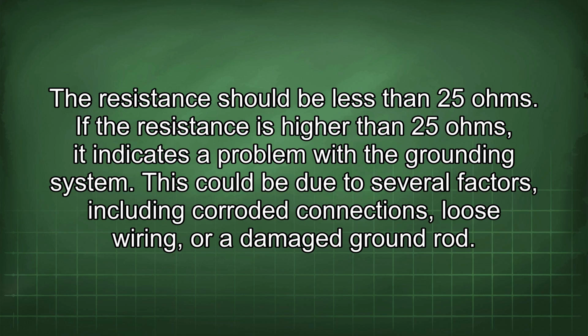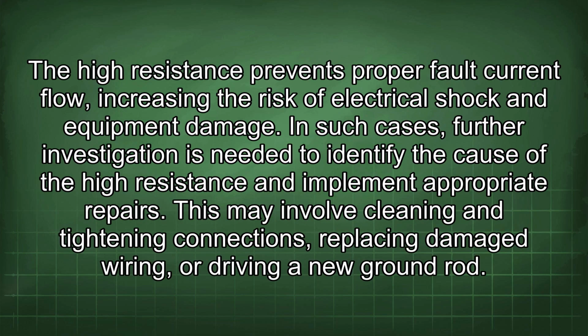This could be due to several factors, including corroded connections, loose wiring, or a damaged ground rod. The high resistance prevents proper fault current flow, increasing the risk of electrical shock and equipment damage. In such cases, further investigation is needed to identify the cause of the high resistance and implement appropriate repairs. This may involve cleaning and tightening connections, replacing damaged wiring, or driving a new ground rod.